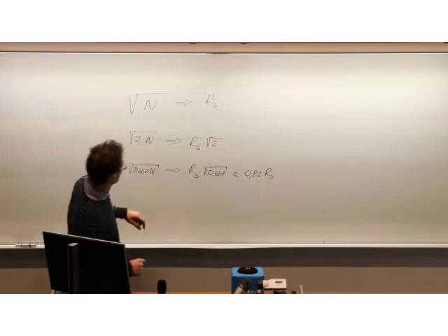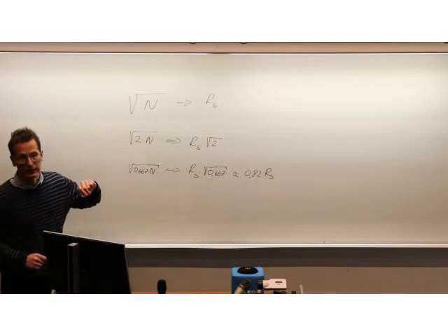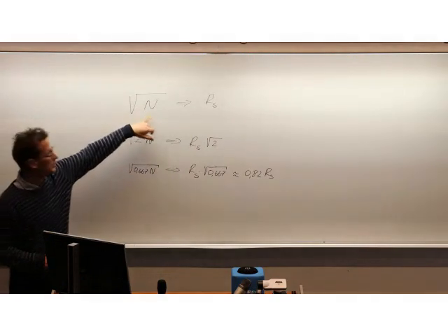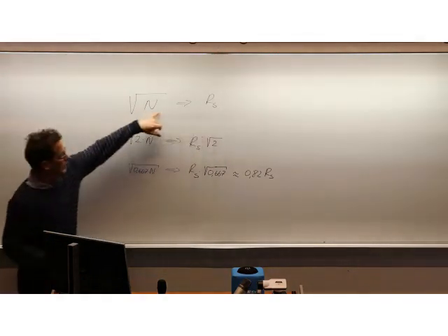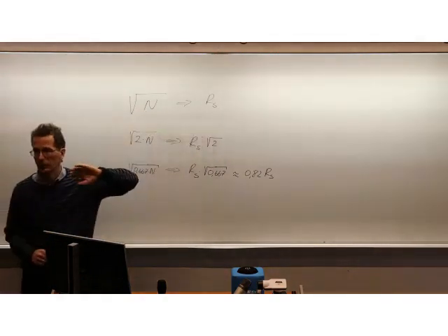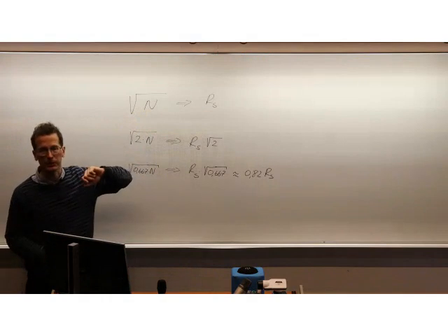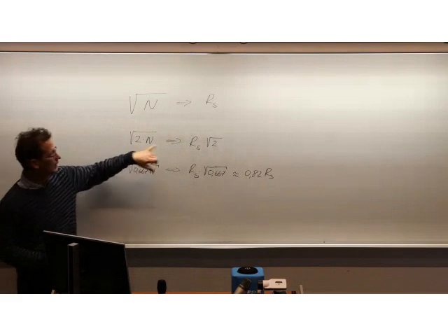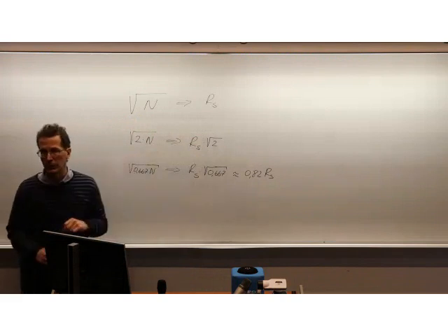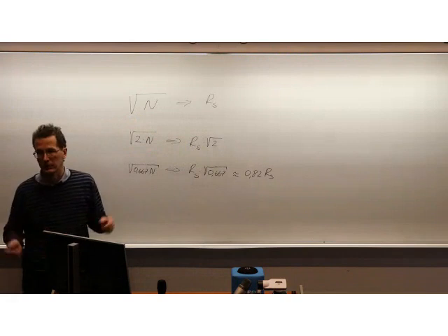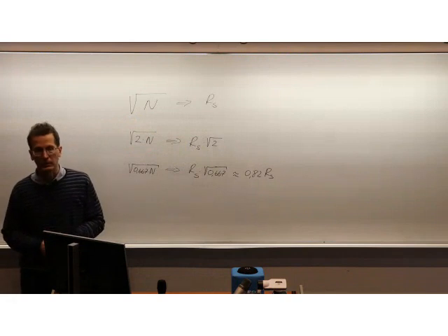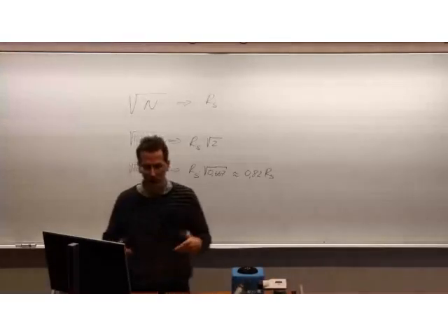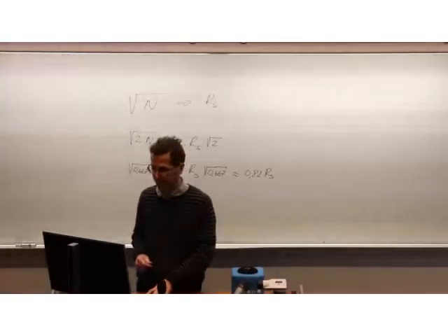And also the reverse: if the initial peak resolution is not good enough, and we see that we need better separation of peaks, then we can use a 2 times longer column and can expect 1.4 times better peak separation. And this helps us, then we have achieved our goal.